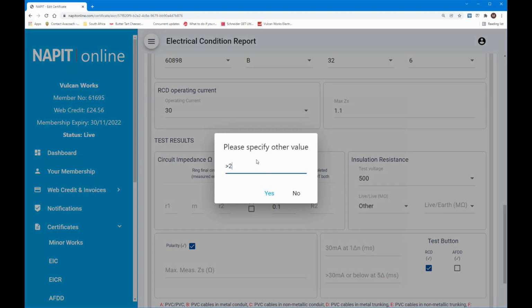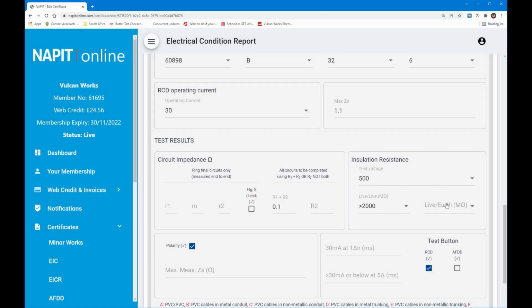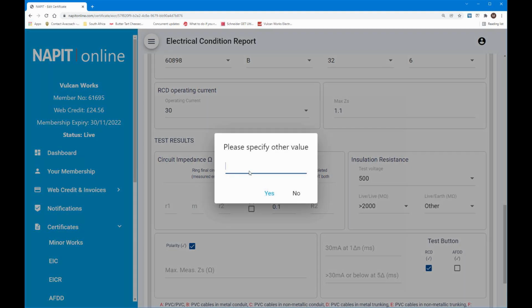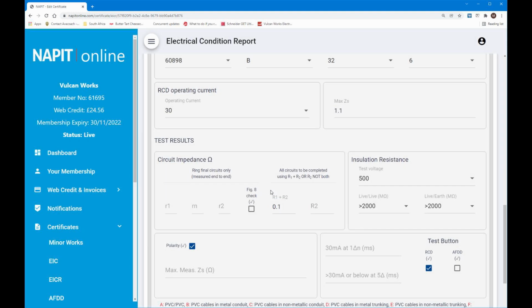So, and it was absolutely fine, as it should be, because this was done as a rewire not so long ago. So I'd be hugely surprised if you didn't do that. So that was absolutely fine. Polarity test was fine, and the maximum ZS would have been 0.1 plus the 0.33 we got for the ZE, so that's 0.43, which is well within the max ZS. So it passes, that's fine.